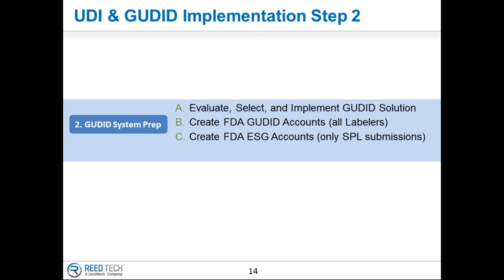Vicki asks: if a kit contains three different devices and one out of three is exempt from direct marking, should the kit be submitted with 'device subject to direct marking but exempt' selected as yes? What we have seen is the FDA take the most cautious, most extreme high-risk component and report on that. So yes, the overall kit should be identified with direct marking. Similarly, if a kit has one product that needs sterilization, the FDA would use that rule of thumb: take the worst-case component and report the system-level kit at the extreme level.